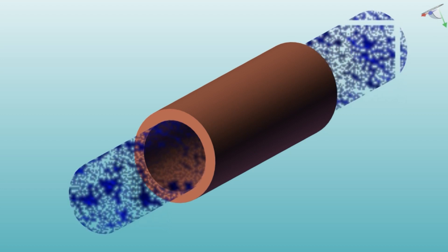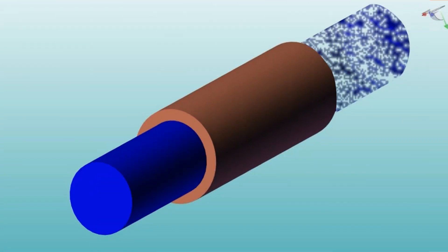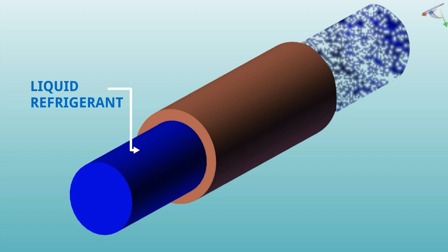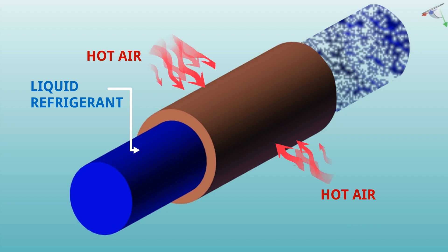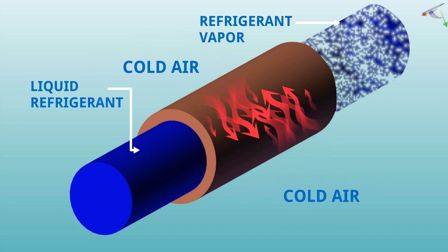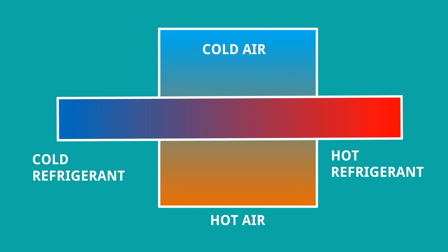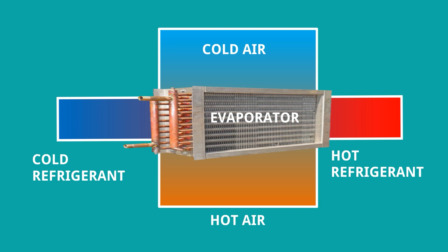Let's understand how heat transfer happens through the refrigerant pipe. This is a liquid refrigerant inside the pipe, and outside the pipe is hot air. The refrigerant takes heat from the hot air and is transferred into vapor. By losing heat, the air becomes cold. So here, cold refrigerant changes into hot refrigerant, and hot air changes into cold air — and this heat exchange between refrigerant and air happens in the evaporator.